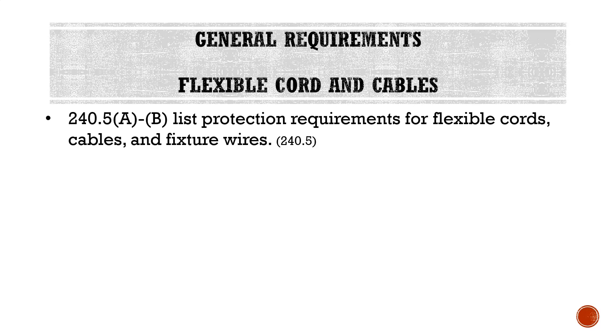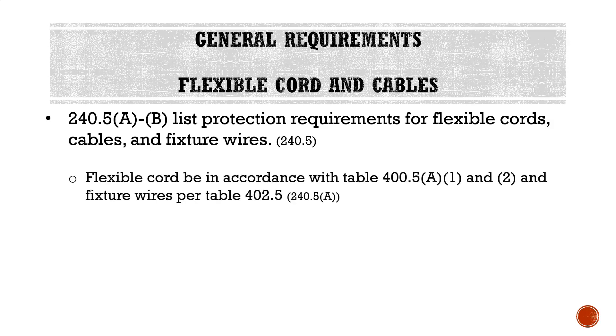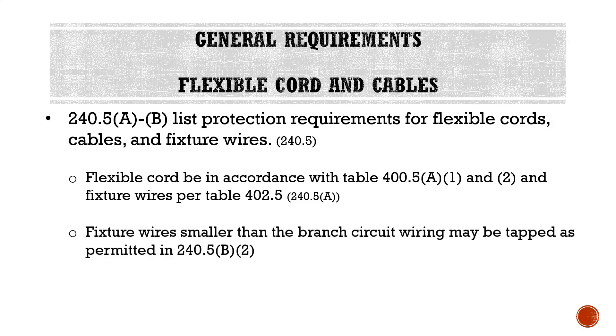Moving on to flexible cords and cables: Section 240.5 A through B lists protection requirements for flexible cords, cables, and fixture wires. Flexible cord must be in accordance with Table 400.5 A1 and A2, and fixture wires per Table 402.5. Fixture wires smaller than the branch circuit wiring may be tapped as permitted in 240.5 B2. This refers to the fact that most fixtures you buy have wiring built in that is a much smaller wire size than the branch circuit conductors — and 240.5 B2 specifically permits that if it's in accordance with the rule.